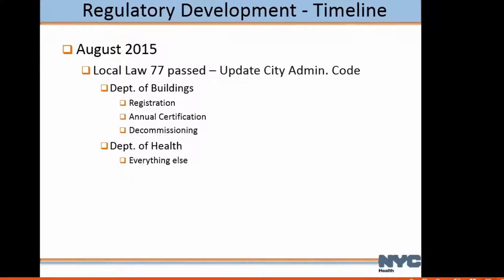What actually did happen in New York City? The outbreak was in August 2015, local law was passed, updating the city administrative code. It did it in three ways. The Department of Buildings — not the Department of Health — got the power to start a registry and check on annual certification of cooling towers. There's a self-certification that cooling tower owners send in every year saying they're trying to be in compliance, and they also handle decommissioning. Registration, annual certification, decommissioning — all Department of Buildings type of stuff.